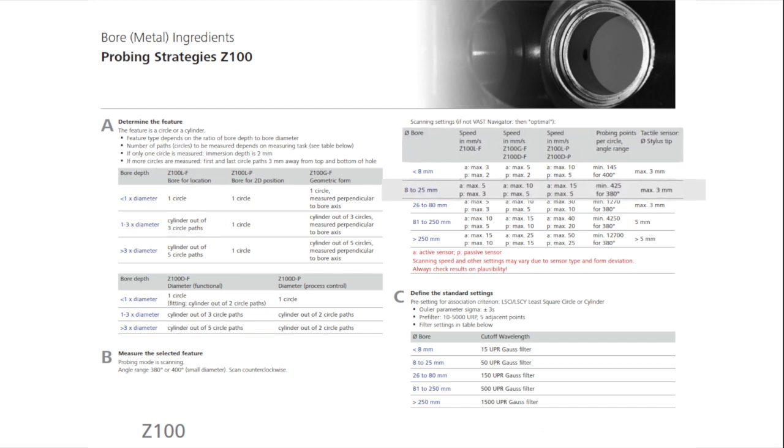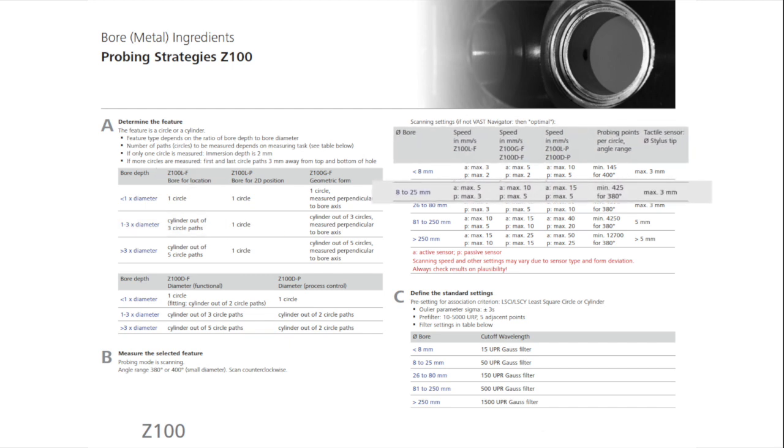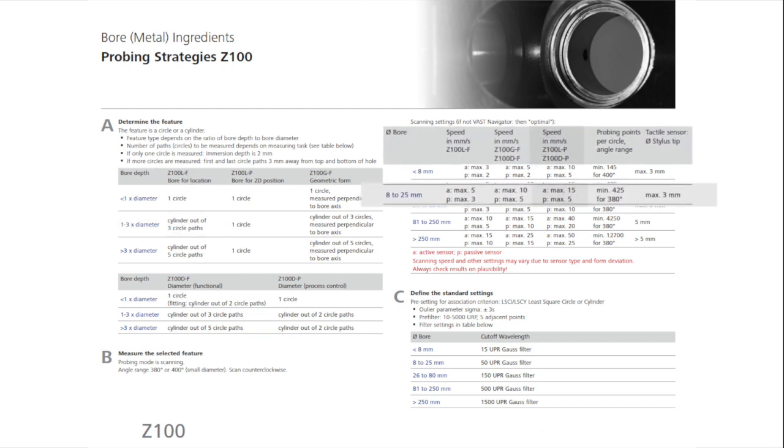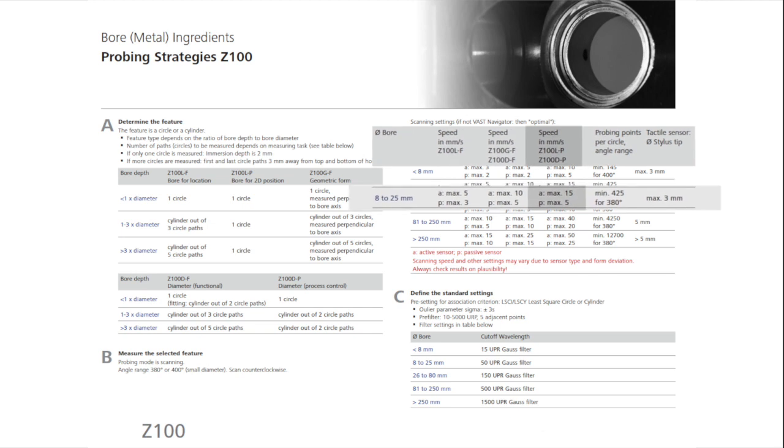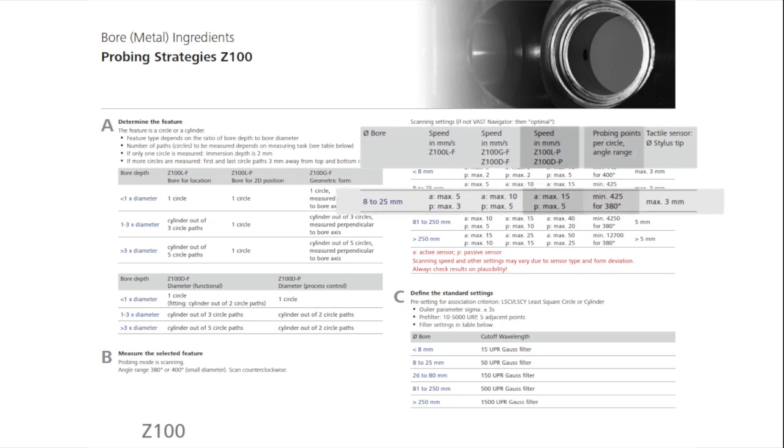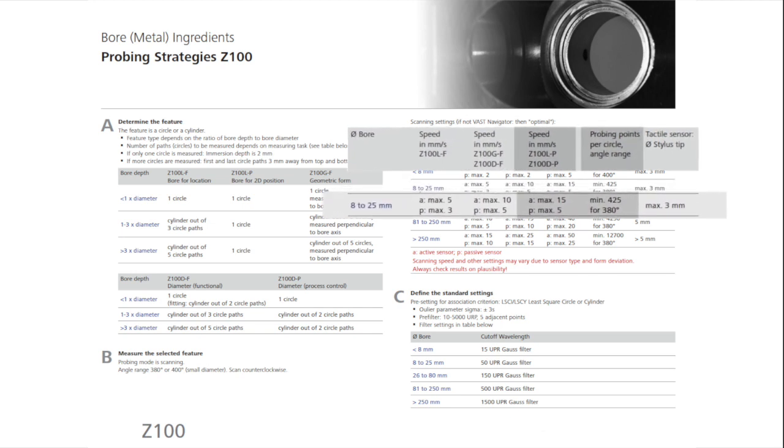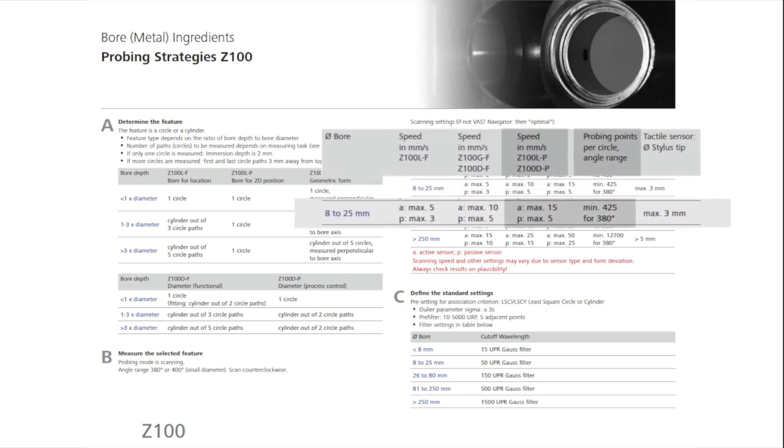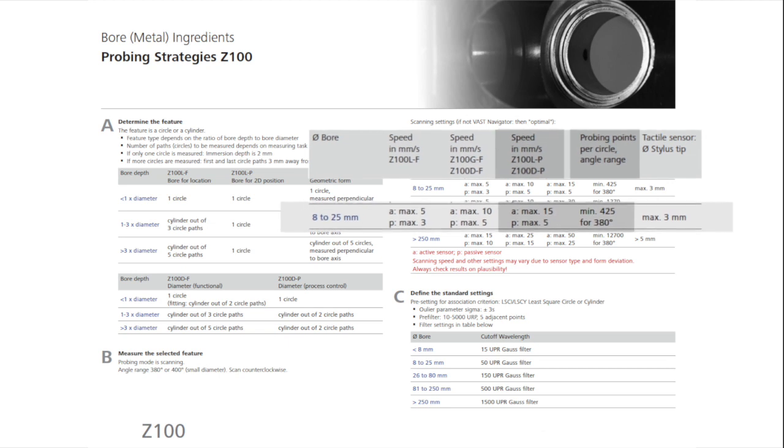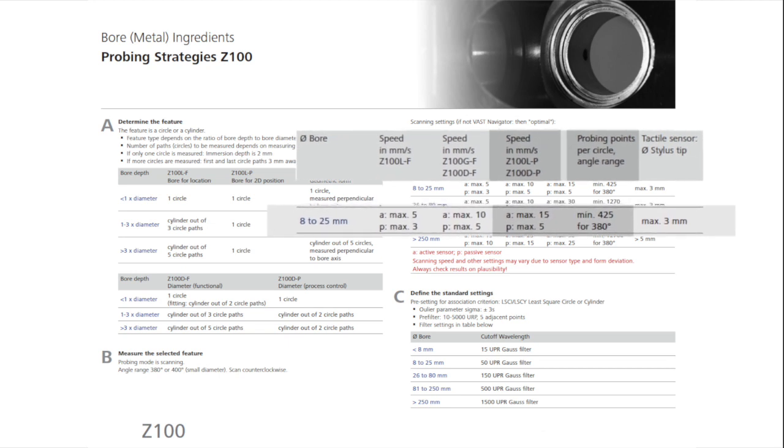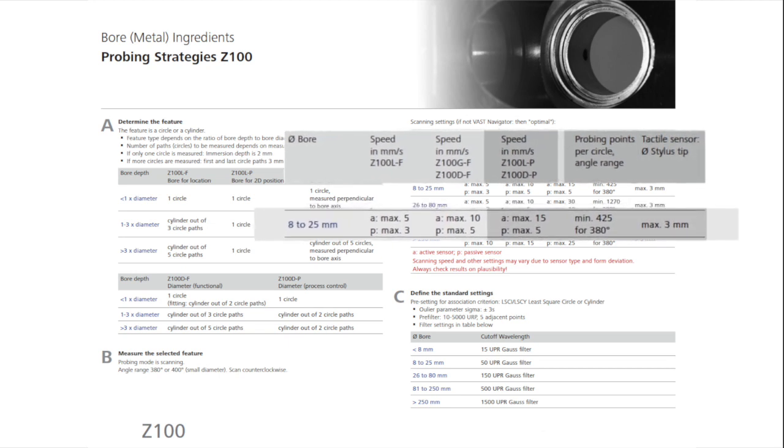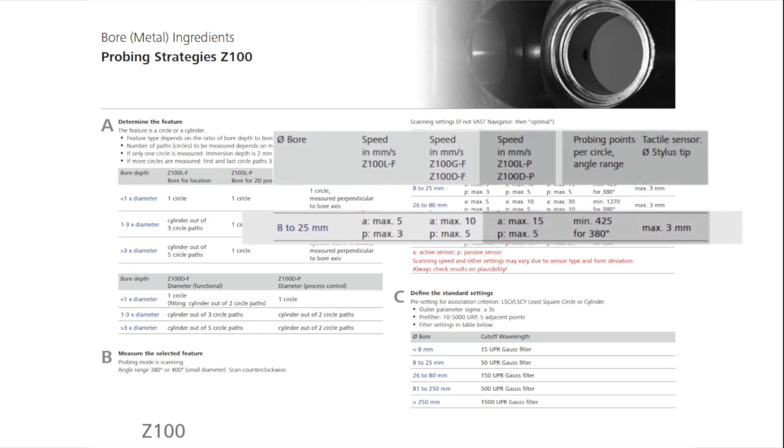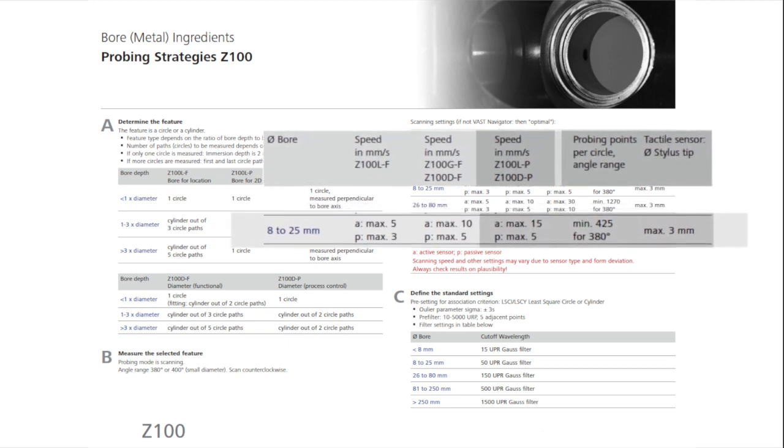You will measure with a maximum scanning speed of 15 mm per second and 425 points on a 380 degree circle path. The diameter of the stylus should not exceed 3 mm.